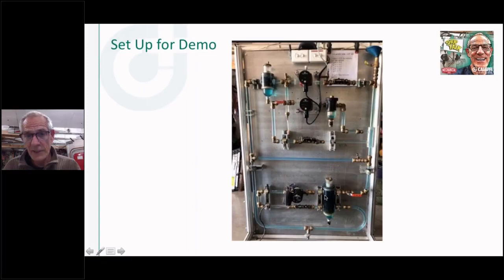Then over here, I put a secondary loop. So I just put a little circulator. I can vary the speed of the circulator here. I've got a flow setter here that I can see what the flow rate's going through there. And I've got a flow setter up on this primary loop, so I can change the flow on these, and you can see the change in the pattern here.